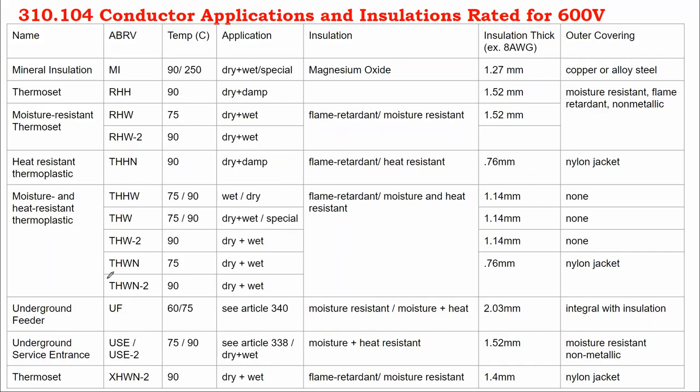And so before there was a solar industry specific cable, we were using a lot of say USE-2 cable in solar because it was thick enough that we could find it with a thick cable gauge. A lot of this THHN and THWN is done at smaller cable gauges or utility scale cable gauges. And this has a wet rating, sunlight resistance rating.